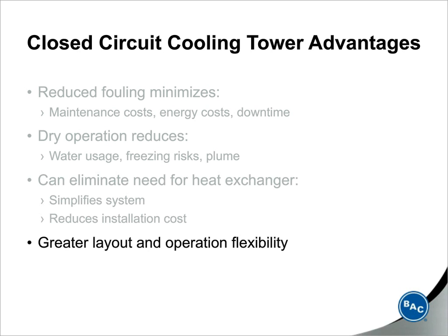Closed-circuit towers are also great for layout flexibility and simplify installation. Open towers are always located at the highest point in the piping system in order to function properly and make sure that the basins don't overflow. Closed-circuit cooling towers, since you have a pressurized process loop going through the coil, can actually be placed at any point in the system, including at grade level, so it can really help out when flexibility is required for layout, depending on the job site requirements. Also, just one last thing that I want to mention that's not on the screen: for systems that benefit from high turndown levels, closed-circuit cooling towers can handle a very wide variation in system flow.